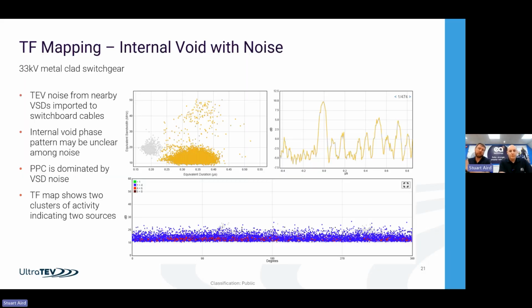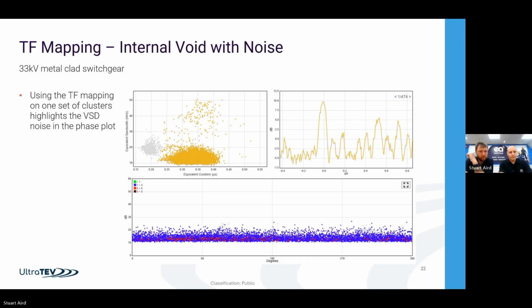Noise. So noise is always a challenge for PD, and variable speed drives are particularly troublesome. So in this instance, you can see a phase plot across the base. It's a TEV phase plot. If you're very attuned to it, you can probably see there are two clusters in there, just about concentrating within the noise. That isn't easy to see, and certainly on site, I think I'd be guilty of skipping over that occasionally. Going back and looking at the offline analysis, we can use this software tool to separate out the different PD. So if we go on to the next slide, you can see here there are two clusters, or three clusters really, in this top left hand graph.